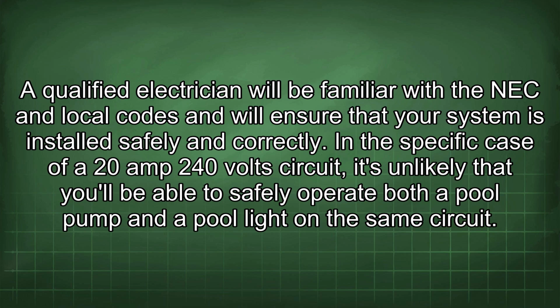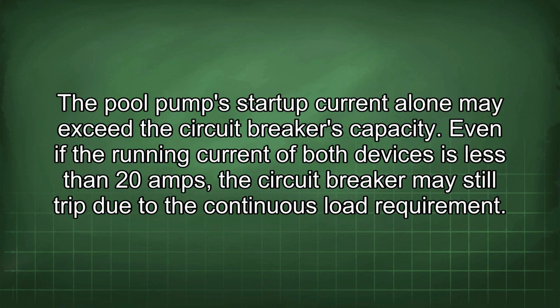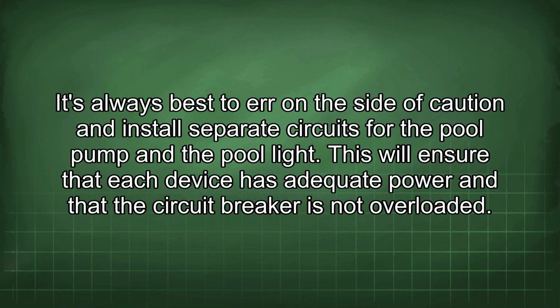In the specific case of a 20 amp 240 volt circuit, it's unlikely that you'll be able to safely operate both a pool pump and a pool light in the same circuit. The pool pump startup current alone may exceed the circuit breaker's capacity. Even if the running current of both devices is less than 20 amps, the circuit breaker may still trip due to the continuous load requirement. It's always best to err on the side of caution and install separate circuits for the pool pump and the pool light. This will ensure that each device has adequate power and that the circuit breaker is not overloaded.